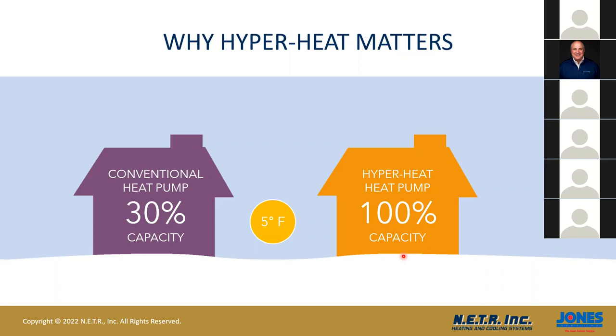You're at 30% of the capacity. We're still at 100% of capacity, giving you what you need to heat your home at that time. So at minus 13 degrees, which we really don't get a lot of, you're still at 76% of the capacity. And we do have heat pumps that are 100% now at minus 13, but they're very limited. They're only in about 4 or 5 models, right? We don't have that throughout the line right now, but I do see that coming, okay?